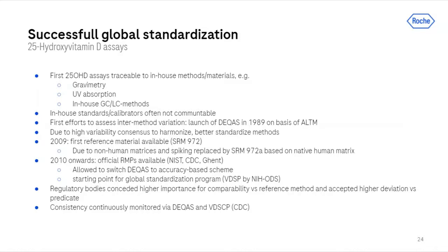In parallel, the Office of Dietary Supplements of the NIH set up a vitamin D standardization program based on the split sample measurement design. As the different methods had to adjust their standardization to meet the reference, comparability to potential predicates was lost to a greater or lesser extent. However, regulatory bodies accepted and acknowledged that comparability to the higher-order reference method is the desired goal. The consistency and comparability is continuously monitored by assessment schemes provided by DEQAS and also by the CDC.